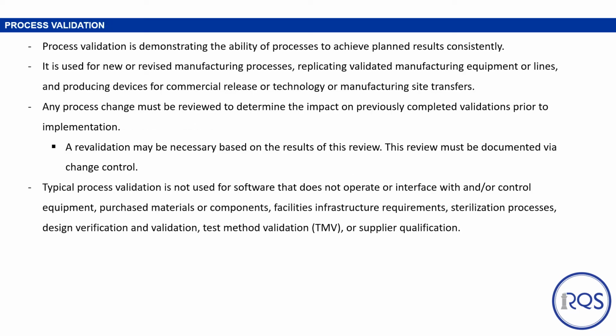So once a process has been developed and we have taken into consideration all of the items that we just discussed, we can now move into process validation. Process validation is demonstrating the ability of processes to achieve planned results consistently. It is used for new or revised manufacturing processes, replicated, validated manufacturing equipment or lines, producing devices for commercial release, and technology or manufacturing transfers. Any process change must be reviewed to determine the impact on previously completed validations prior to implementation. A revalidation may be necessary based on the results of this review, and of course, this review must be documented in the change control system.